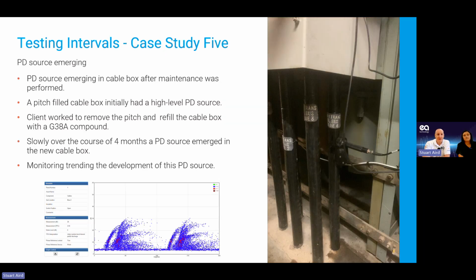And then this is another case. They had high levels; they put a new cable termination box in and decided to monitor it from day one. And within 4 months, this PD source started to emerge. So we started to see this void within this. They put a G38 compound into that cable termination box. But if you haven't got it in quite right, and you've got any little air pockets within there, at first it might seem fine, but then as time goes on, you'll start to see these activities, and you can see there's probably multiple air pockets, because if you look at this phase resolved pattern, we're getting different lines and different areas. So that could indicate that there's different little air pockets within that insulation.